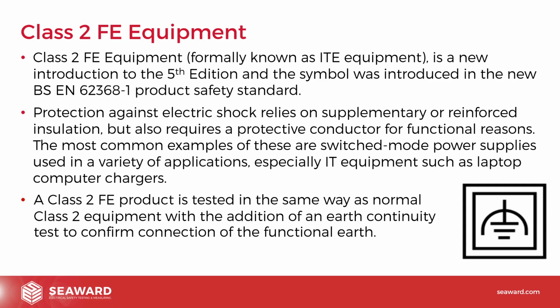So the duty holder may do a risk assessment and decide, actually, in addition to the normal Class 2 tests, we want to do a continuity check, a functional check on the functional earthing. Obviously, that can be carried out with a continuity tester. And I'll talk later on about some of the changes we've made to the Seaward products, but on a majority of the products, we've added in a test sequence for Class 2 FE, so you have got a way of testing Class 2 FE.